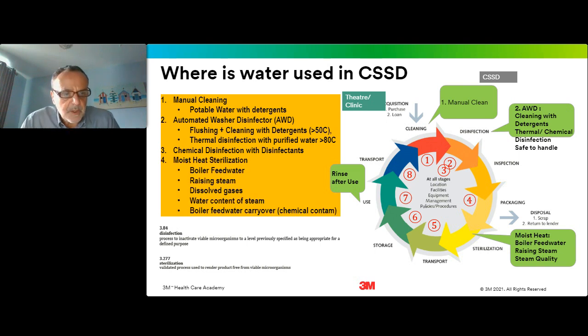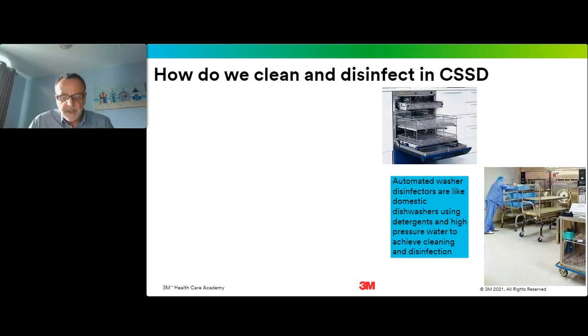And then, of course, we go to moist heat sterilization. The majority of reusable medical devices are sterilized in steam. And, of course, steam is essentially water in its vaporous form. So we also need to consider the quality of the water that's used to create the steam, but also the quality of the steam itself. And in looking at this, we need to consider boiler feed water quality, what impacts the quality of steam as we raise the steam, dissolved gases, the water content of the steam, and boiler feed water carryover. We'll consider this in more detail as we go through the presentation. So how do we clean and disinfect surgical instruments in the decontamination department, the SSD?